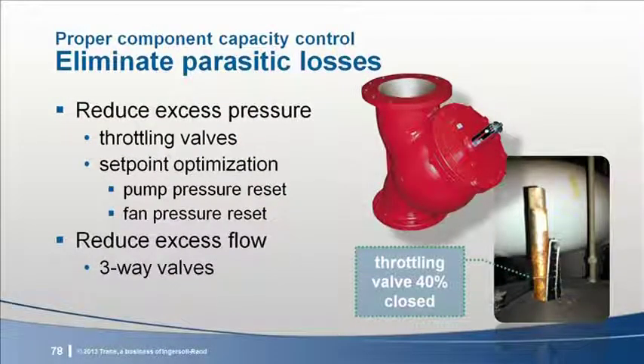One last form of parasitic loss to talk about is excess flow. Again, not often thought of as a parasitic loss, sending chilled water out in a variable flow system only to have it flow through a bypass wastes work performed by both the chiller as well as the pumps.